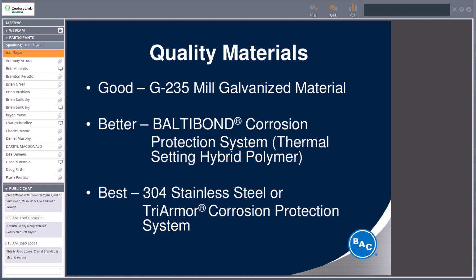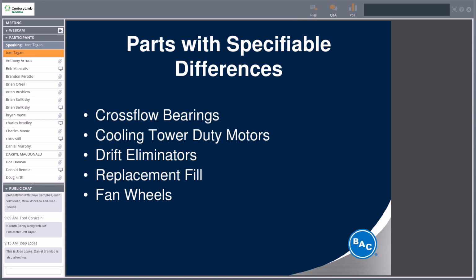Quality materials, again, if you are ever involved in the discussions leading up to a new project, we've got basis of design. We use G235 galvanized material. We also have a corrosion protection system that we would apply over that. And then you can also go to 304 stainless steel, or again, a Tri-Armor corrosion protection system. That's a polymer coating on top of the galvanized. We recommend, especially in New England, where most of the specifications we see at a minimum call for a 304 stainless steel cold water basin. The cold water basin is the most expensive component of your cooling tower, and if you add the fact that you have to get a crane to remove it to replace it, it makes sense to upgrade that material on new projects.